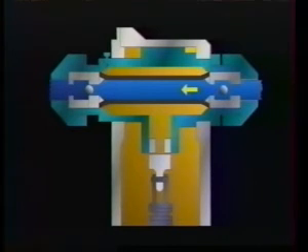At either end of the diaphragm there are non-return valves — one inlet and one delivery — which control the flow of water through the cylinder. On the upstroke of the piston, the diaphragm is pressurised and causes the inlet valve to close and the outlet to open. On the downstroke of the piston, the opposite happens, with water being drawn into the diaphragm through the open inlet valve, whilst the delivery valve remains closed.